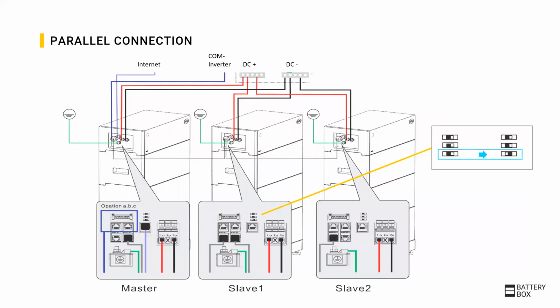The communication cable to the inverter is then from the master BCU to the inverter, exactly as you would do if you only connected one battery. Each battery needs to be grounded, and the DC cables should be collected, and then one DC string will go to the inverter. Here, all DC cables should have the same length and parameters to avoid a difference in voltage on the different batteries.